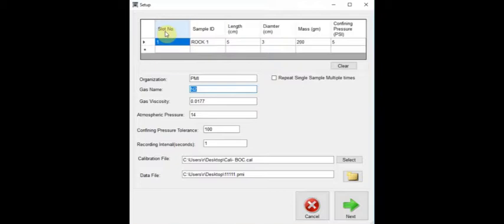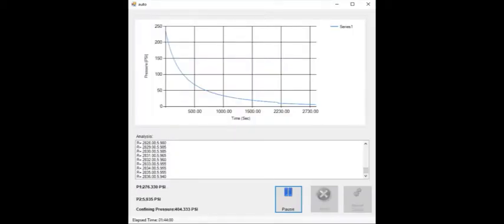If we proceed, a window will open beginning the auto test. In this window we can see a graph that will be populated in real time with data for pressure over time. Below this is a field that records each data point as well as a monitor for pressure gauge 1, 2, and the confining pressure gauge. We can pause or abort the test using manual control if required.